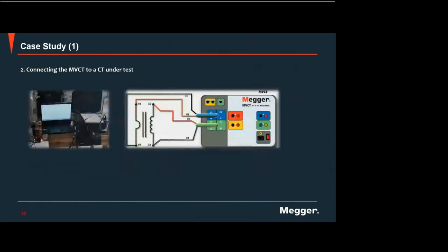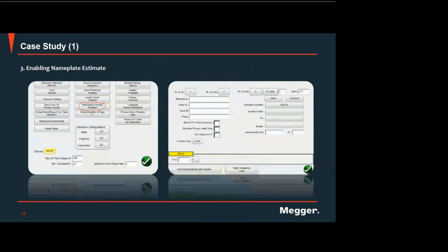Now we are connecting the MVCT to a CT, and the good thing with the MVCT is that it has a displayed diagram on how you connect the equipment to the CT. So it's very simple, very easy to understand. And this is one good thing with the MVCT: we can do nameplate estimate. Meaning, even if you don't input anything on the nameplate values, for example, you have a CT that doesn't have any nameplate, then the MVCT can estimate the nameplate values. As you can see here, we did not put anything in this case study, aside from changing the number of taps because the terminal of the CT is only 2. But of course, you can test up to 5 terminals simultaneously. This is one of the features of the MVCT.